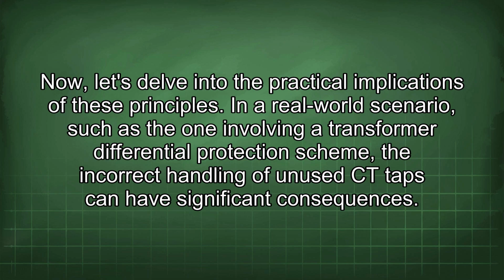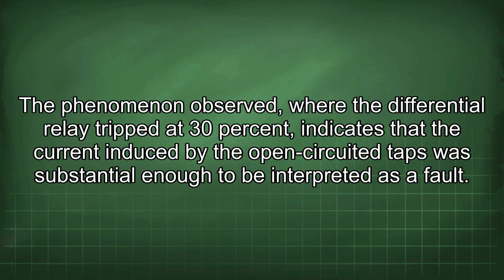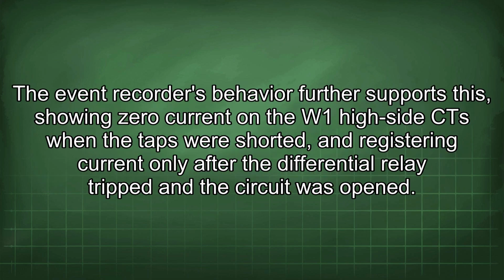In a real-world scenario, such as one involving a transformer differential protection scheme, the incorrect handling of unused CT taps can have significant consequences. The phenomenon observed, where the differential relay tripped at 30%, indicates that the current induced by the open-circuited taps was substantial enough to be interpreted as a fault. The event recorder's behavior further supports this, showing zero current on the W1 high-side CTs when the taps were shorted, and registering current only after the differential relay tripped and the circuit was opened.